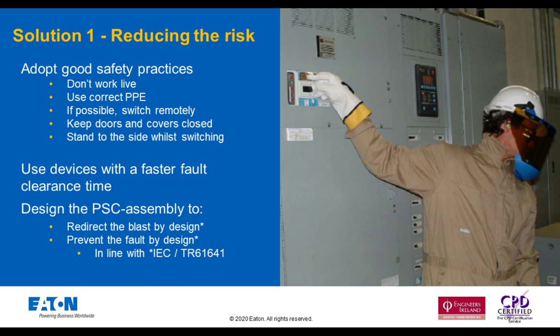And then the other good approach is the design of the PSC assembly, or power switchgear and control gear assembly, as it's commonly known, switchboards or panel boards. We can change the design to redirect any exhaust gases or pressure, with pressure relief flaps in the switchboard to put the gases away from the personnel whilst switching operations are taking place. Or the other good thing is by design, and that's implementing the product standard of 61641.